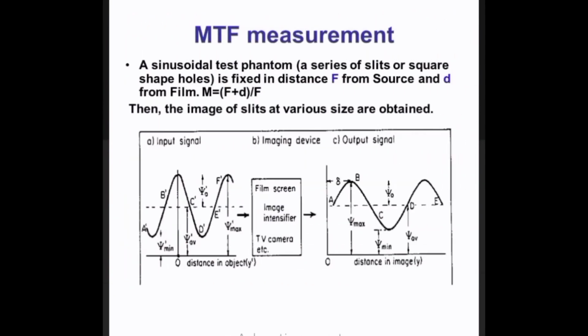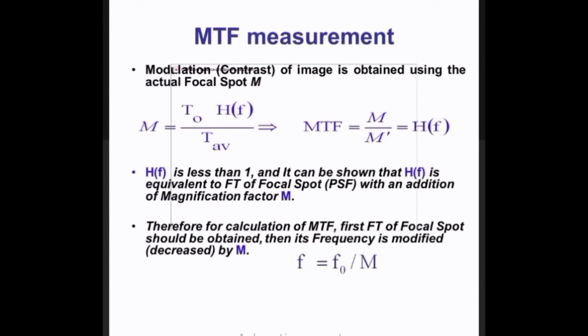On the diagram, objects having different sizes and opacity are displayed with different grayscale values. What is the modulation transfer function used for? The modulation transfer function, or MTF, determines how much a contrast in the original object is maintained by the detector. In other words, it characterizes how faithfully the spatial frequency content of the object gets transferred to the image.